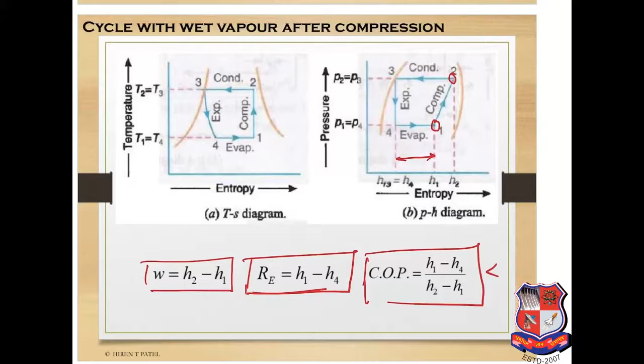continues. Here also it's the same: work is H2 minus H1, refrigerating effect is H1 minus H4, and COP is RE divided by W. But the difference is that the refrigerating effect obtained is less compared to the previous one, that is dry saturated vapor after compression. So the refrigerating effect obtained will be less, so ultimately the COP will be less. So it is not advisable to use this cycle.